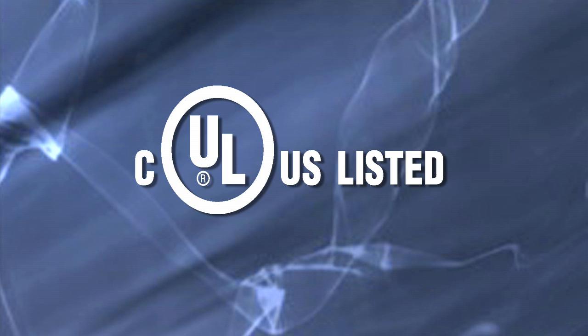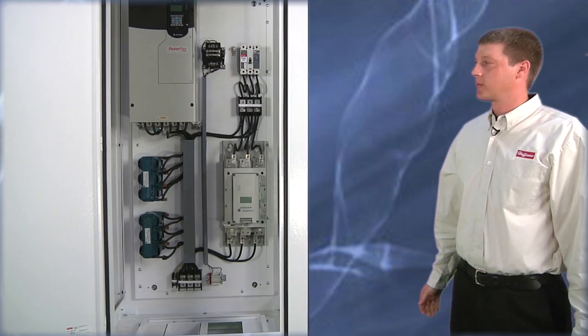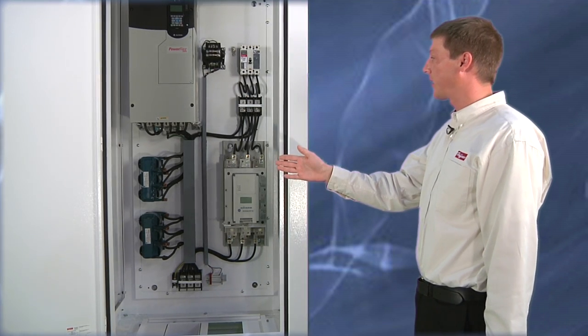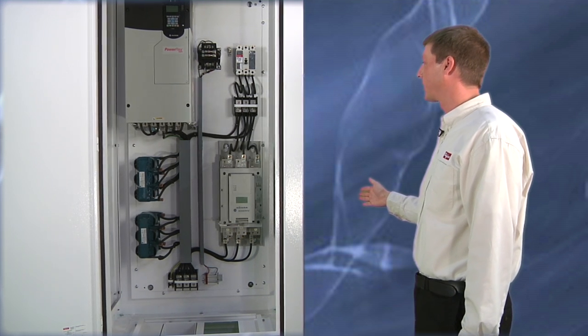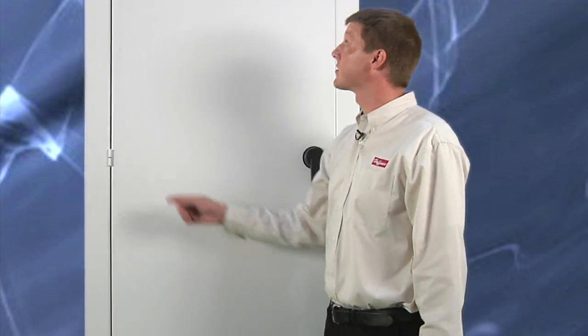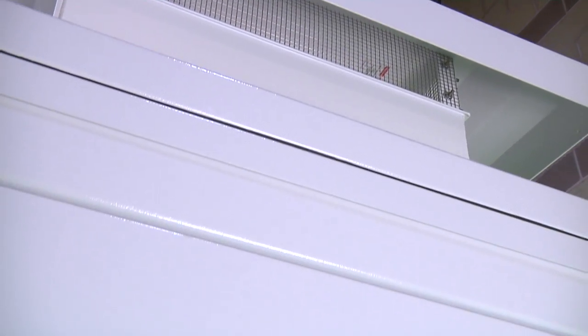The Weatherflow HD enclosure was tested vigorously in our UL certified lab. We load tested the two-door version with 2,000 pounds on the left-hand panel and 400 pounds on the right-hand panel, and saw no distortion. This cabinet is rated NEMA 3R and features stainless steel hinge pins and stainless steel mesh to hold up to harsh environments.